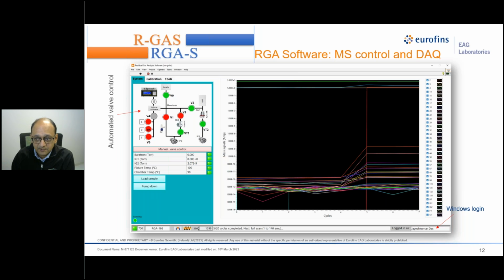And this is how we can do the analysis, either calibration or, in the case of a sample, the same way: we take the background and then we puncture the sample while this valve is open. As soon as you puncture, the gas will be introduced to the sample chamber. When the analyst says proceed, it opens up valve V2 and the gas is transferred to the mass spec system. So this is how the individual components of the RGA system can be described. Each component has a very specific role to play, like checks and balances, to make sure that the test method is being followed and all the data is being recorded.